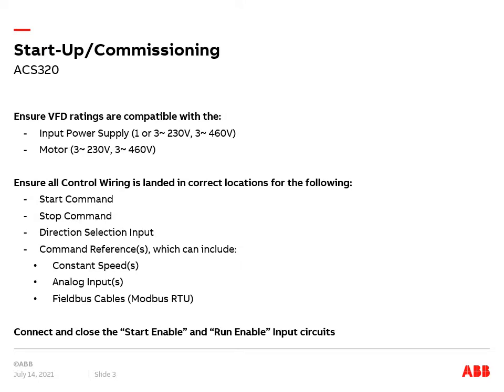When commissioning an ACS-320 VFD, certain items must be confirmed prior to power-up. Two items are the VFD's input power supply level and configuration. Is the supply single phase or three phase? Is it 230 volts or 460 volts?